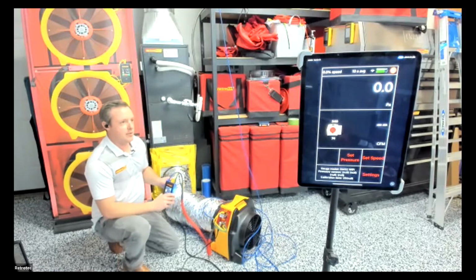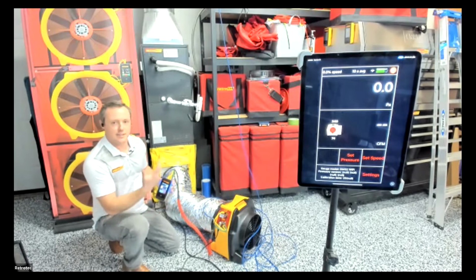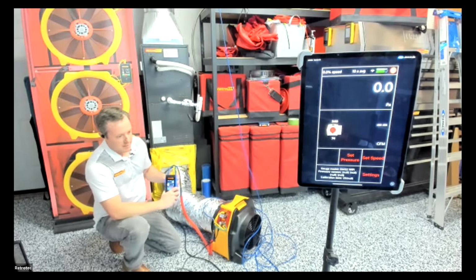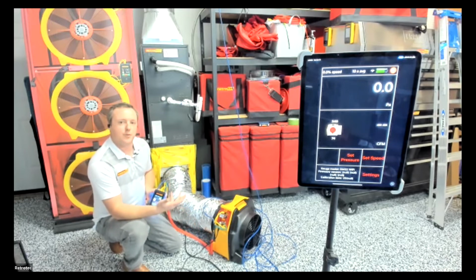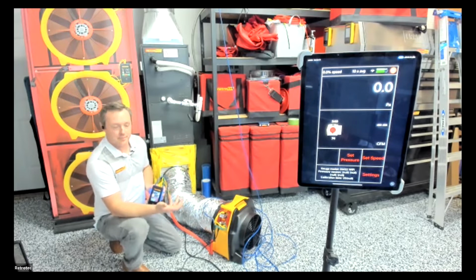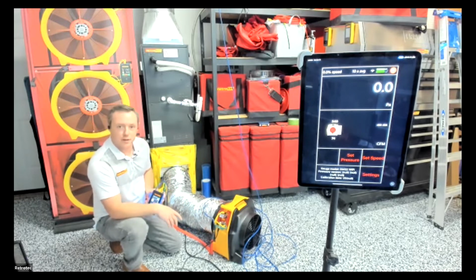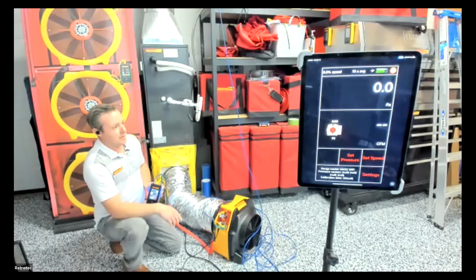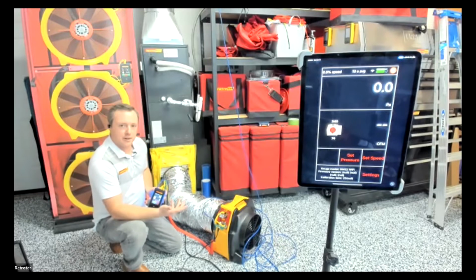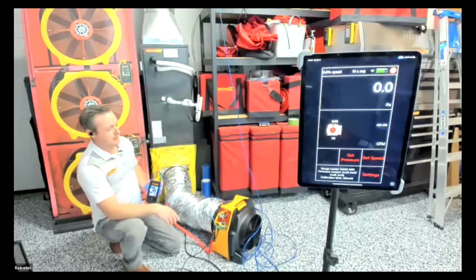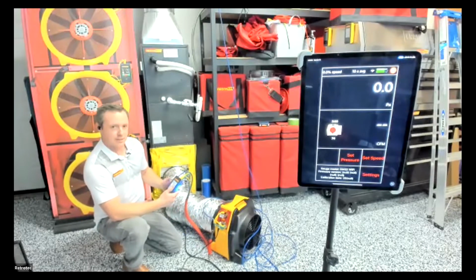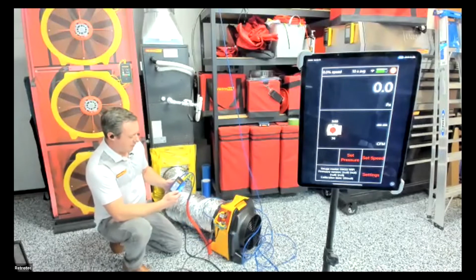And the way we want to interpret our results is, sometimes we'll have a target that we want to shoot for. Say we're testing for code. A lot of times that target is represented as a percentage of the floor area that the system serves. So, say we have a 1,000 square foot home. If our target is 6%, then we want to be at or under 60 CFM. So that's a way to look at that. And there's different ways you can have that represented on the gauge. So we want to have channel A represent pascals for us.